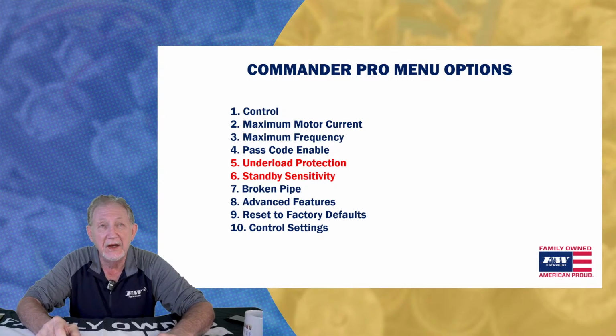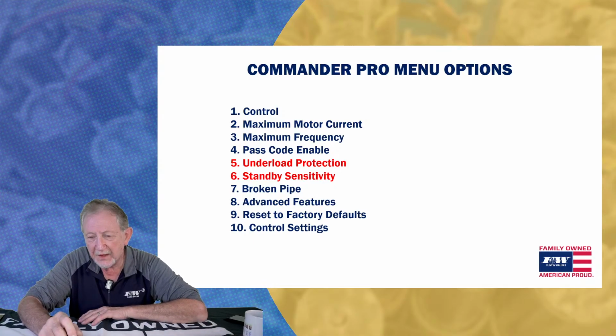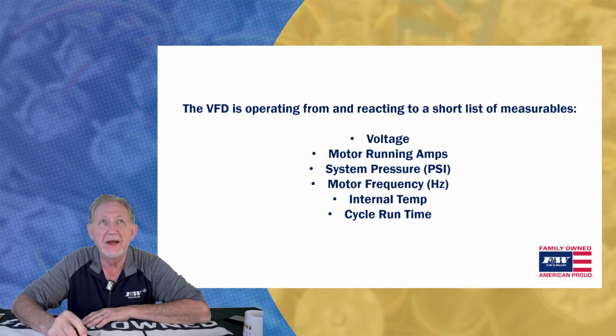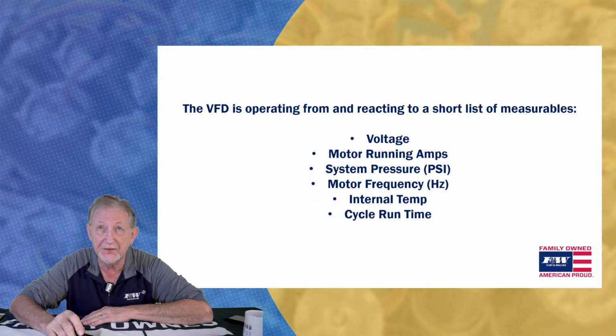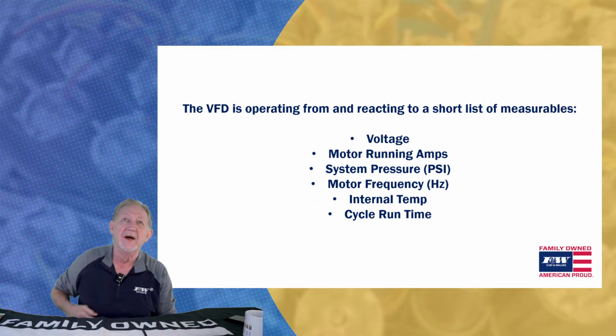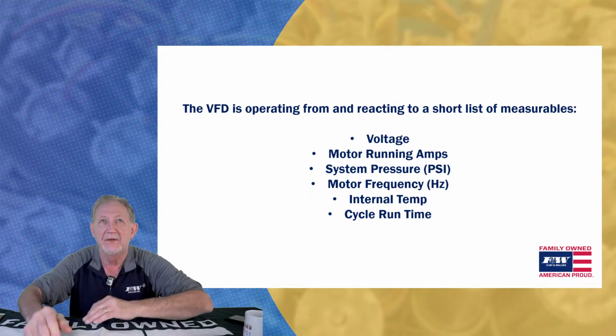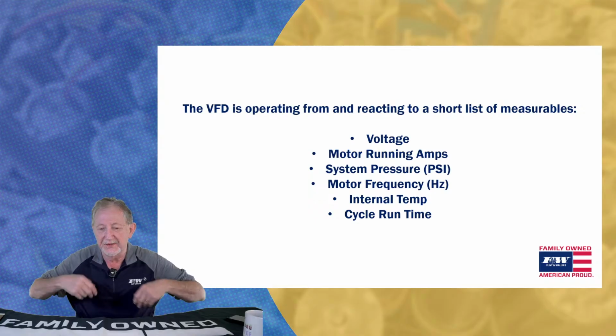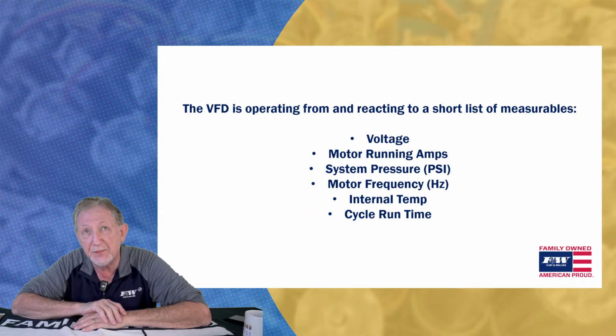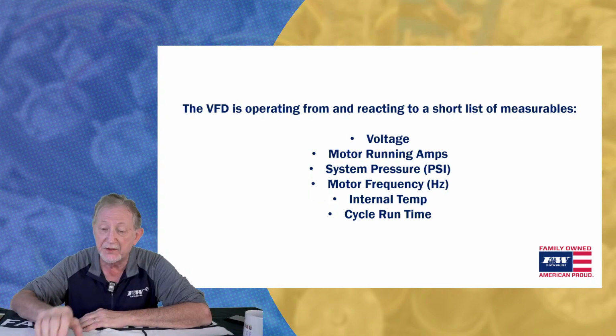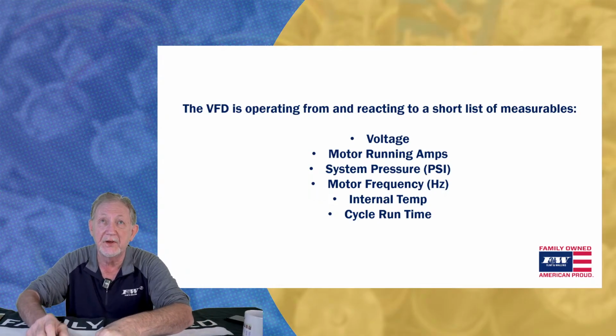So let's go back and just review this underload protection and this standby sensitivity, all right? Underload protection, right? When that VFD is operating, this is true with any VFD, and certainly all the different VFDs Flint and Walling has. These are the measurables. This is the list of things that VFD has the ability to measure. So you see at the top it runs from voltage to the amps to the system pressure, frequency on down to the temperature and cycle runtime. These are the only measurables. On there is not gallons per minute. These drives don't know if you're flowing water or not. They have no idea. It's not something they measure. They only know what's being listed on the screen right there.